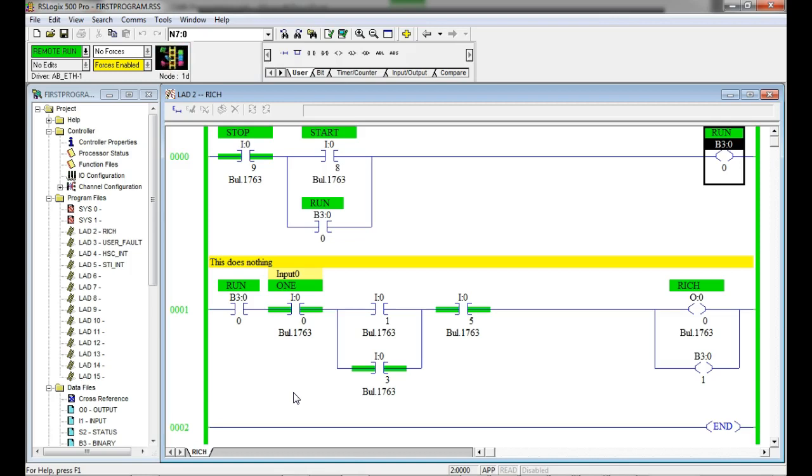This is going to get you backwards if you come out of motor controls and you're used to using the symbol for normally closed contact. You can use it for anything else, you just can't use it for a stop button, because the stop button has to be normally closed. So if I break the circuit, then the motor would stop, right? Okay.